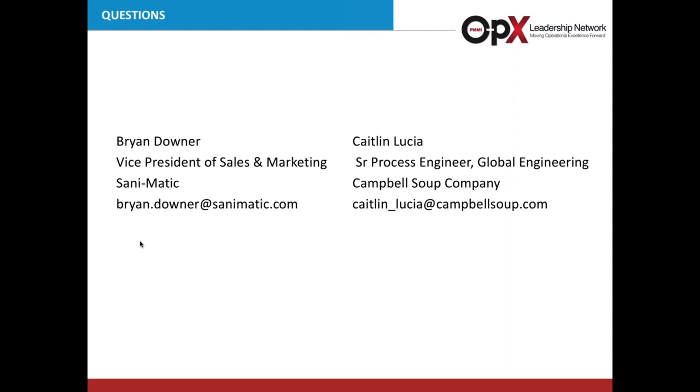Caitlin, how do I make my CIP process shorter and more efficient? That's the hundred-dollar question. You're going to use flow, temperature, concentration, or your particular chemical as levers to decrease your time, within constraints. You can also look at your prep step — are you leaving too much gross contaminant in your system that makes the CIP take longer? Would it be worthwhile to remove more of that through recovery systems, air blows, or other methods before beginning CIP to shorten your overall time?